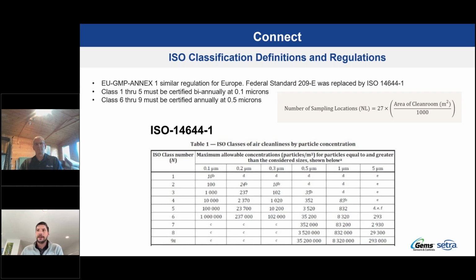And that's really not its design intent. Really, what you'd want to do is identify the most critical spots within your clean room to place your particle counters to take regular samples, so that in between your certification visits your clean room is well within the correct operating conditions. And if you did get a spike in particle counts, you would still receive those real-time notifications that allow you to take corrective action. So pretty much anywhere where product is exposed to open air, where if a high particle count event happened your product would most likely be affected by it, those are the areas where you typically want to mount a particle counter to take regular samples throughout the day.